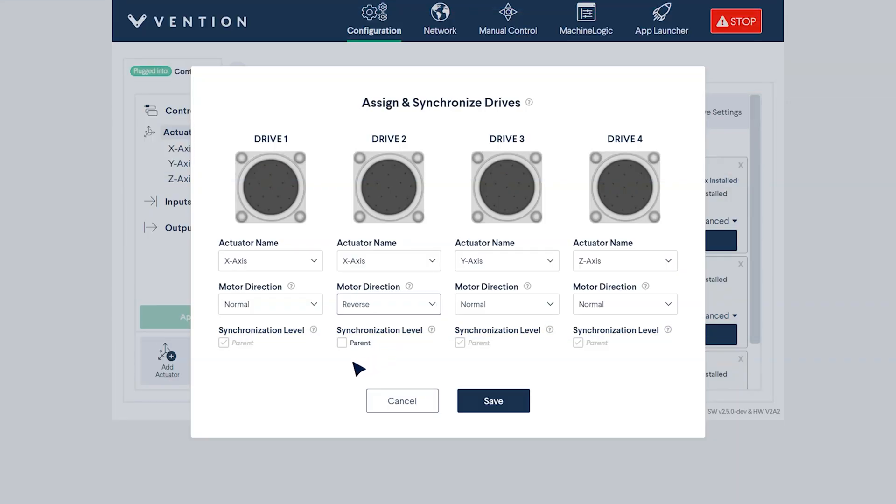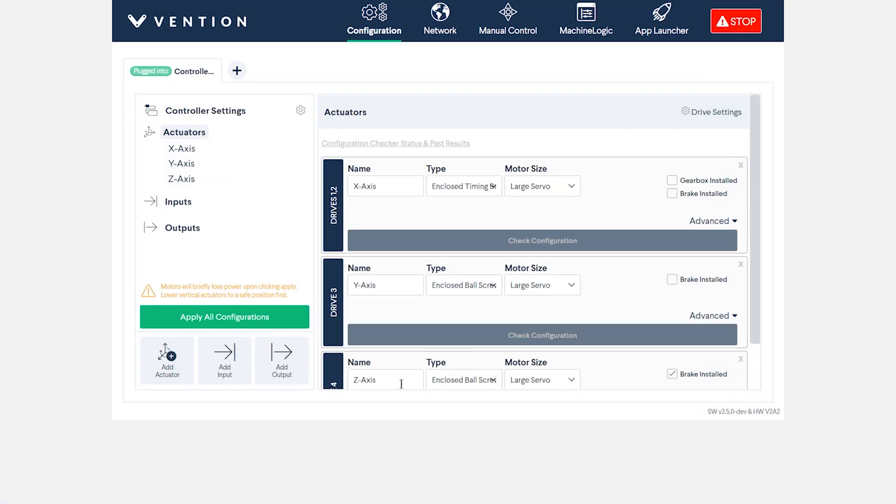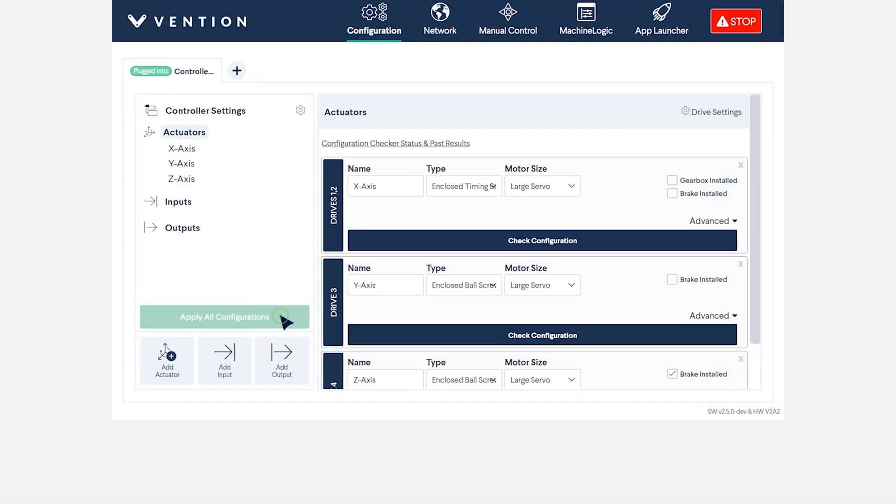In the bottom row, select which drive will behave as the parent and which one will behave as the child. If you're not sure which one is which, the parent will most likely have the actuator with its sensors attached and the child will have the jumpers in place.